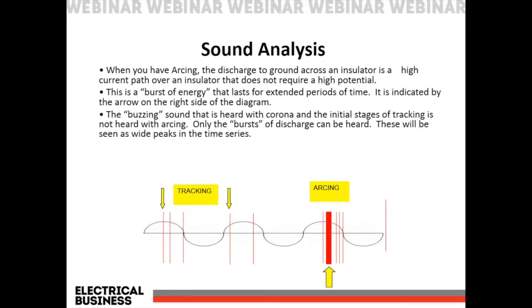It's the same thing as tracking, except that instead of smaller and narrower events or discharges like they were before, we now have larger events, which is noted by the big red bar that's sitting there in the middle of the last part of the sine wave there. So again, when you have arcing, the discharge can go to ground across an insulator.